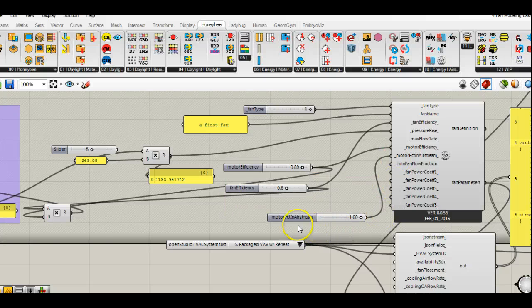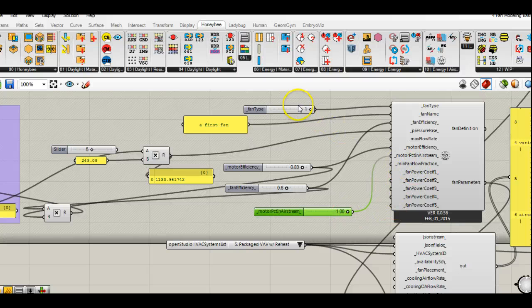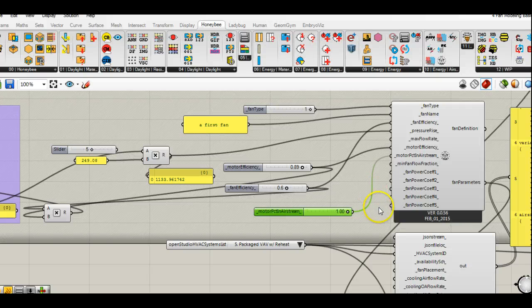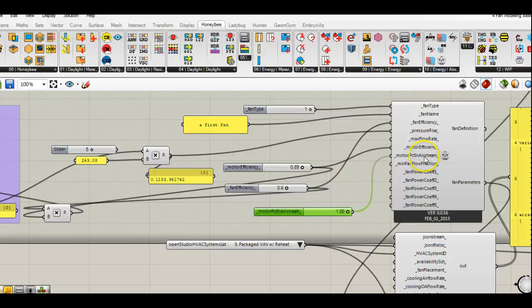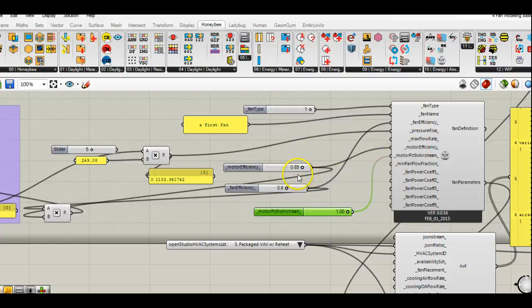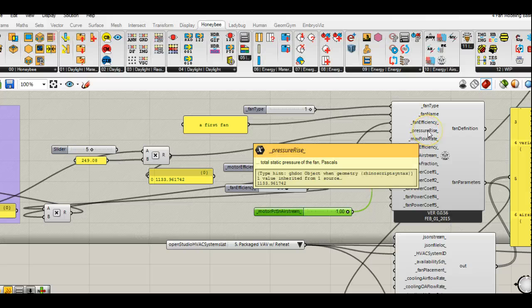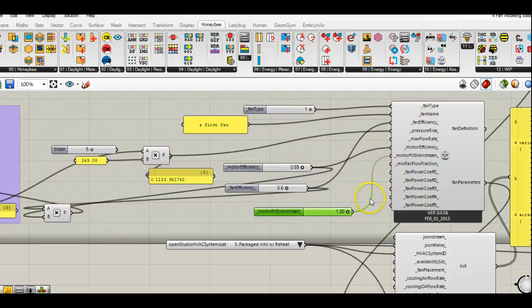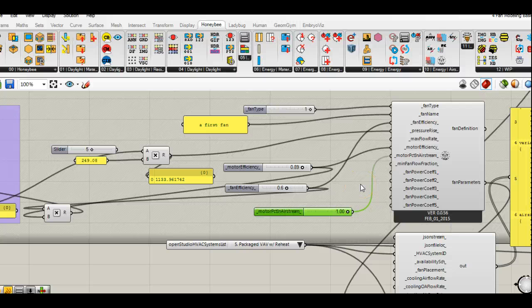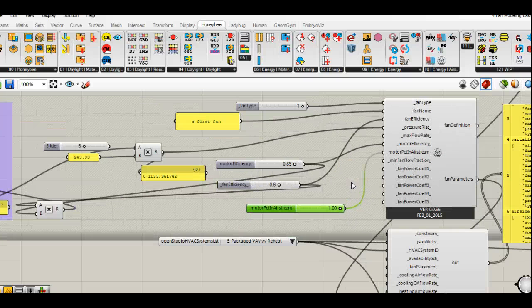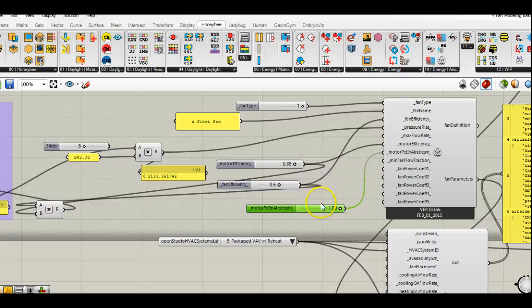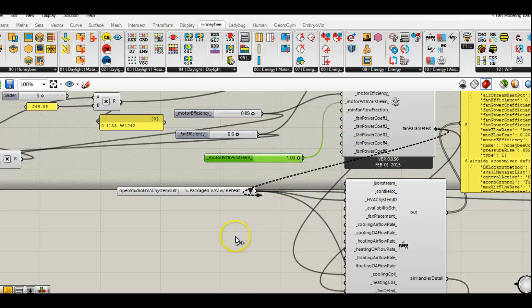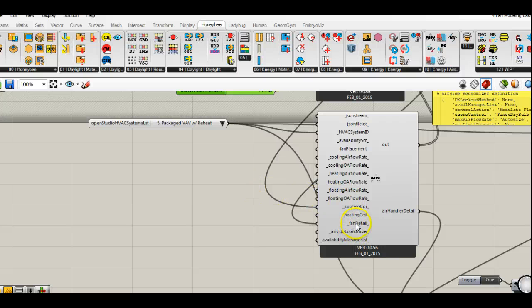A couple other things to mention: if you set the fan type to zero, or in other words constant volume, and you have any values plugged in for a fan power coefficient, those are just going to be ignored. As I've said for a lot of these components, we don't really do a lot of error checking right now, so it might be possible for you to put in a motor efficiency of greater than one. There's no balance checking right now, so you could put in a really big pressure rise or a really weird fan efficiency and it would still run. We're trying to think of a way to do that a little better. That's essentially how it works. Any system that needs a fan should have one specified. After you've specified your fan parameters, just plug it in here to your fan detail.